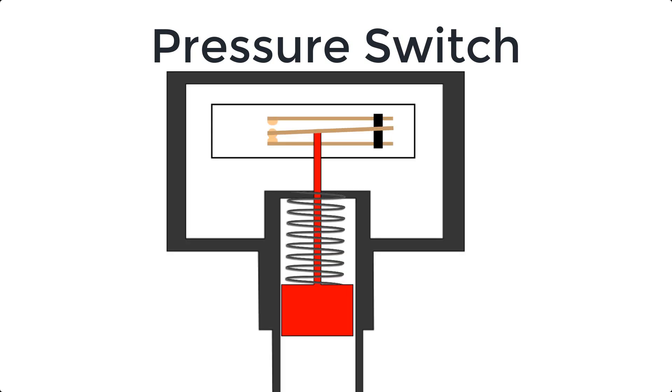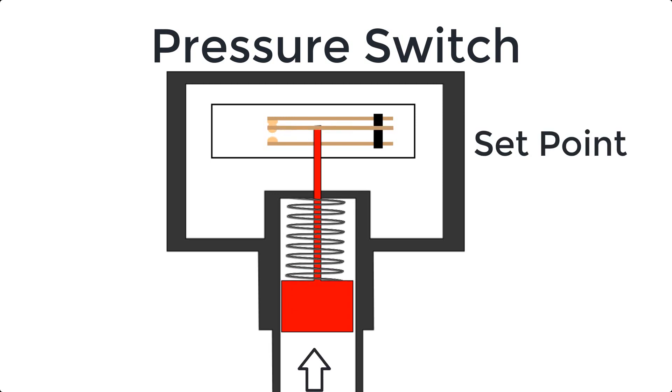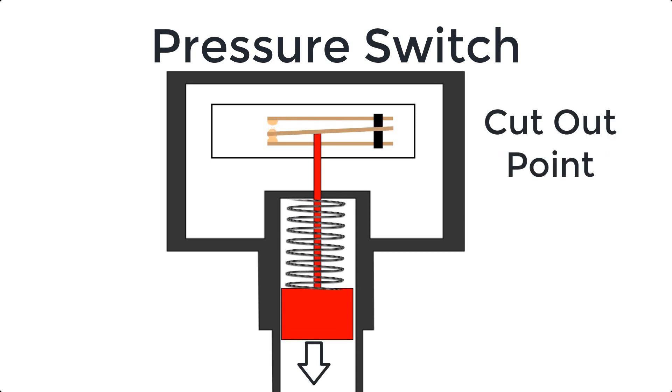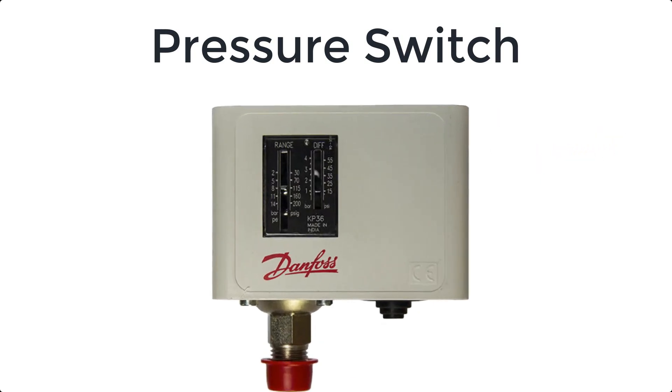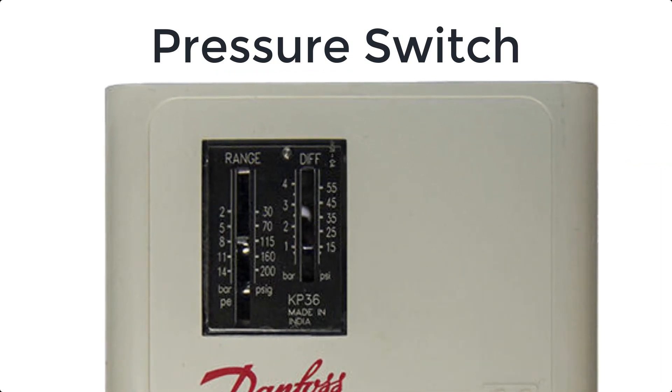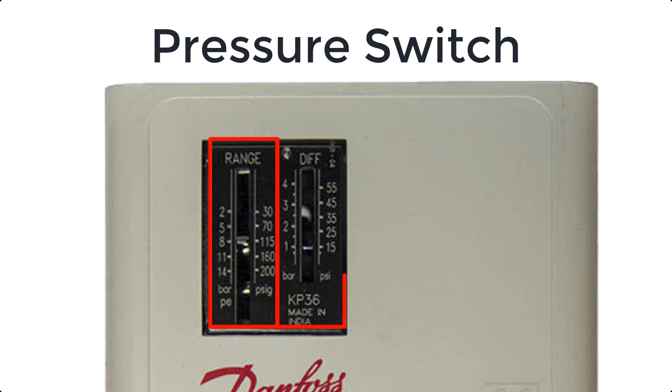The pressure point that activates the switch is called its set point, and the pressure threshold that deactivates the switch is called the cutout point. There are two adjustments on a pressure switch: one is called range and other one is difference. We can set the maximum required pressure through range setting.